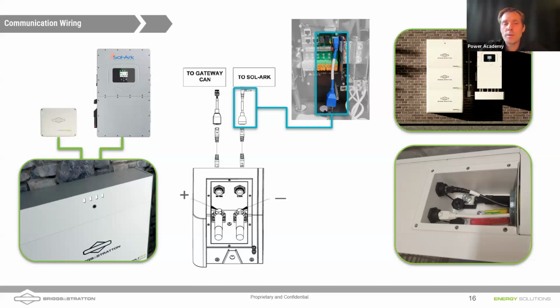To clarify, we are speaking about AC amperage output right now, or at least I am. So I wanted to clarify. The Sol-Ark can absolutely handle 250 amps of DC current coming from the batteries, but that's not, I think, what he's asking. The output of a Sol-Ark on the AC side is going to be limited to 50 amps of continuous output power. So if you need 200 amps of continuous output power, you would need to parallel 4 Sol-Ark 15Ks to do that. If you need just to surge to 200 amps of output power from the batteries, you could do that with 2 Sol-Arks, and they could provide 100 amps of continuous output power, but 200 amps of surge.